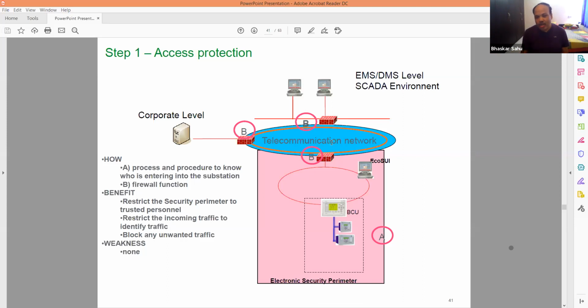So it allows only that particular level of information to pass through; it will not let other things through. For example, in this network I may have some voice communication, data transmission, or other information not relevant for this station or that one. So what the firewall does is block all those things, allowing only what pertains to the SCADA environment, the control center, and the substation to pass.